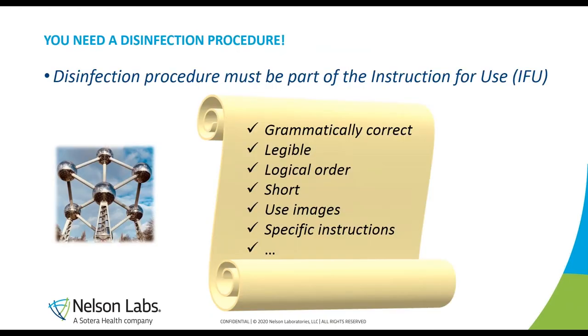Before we start, you need a disinfection procedure. If you don't have any procedure to validate, we cannot start our journey. You must have a procedure, and it must be part of your instructions for use. The information in your instructions for use should be logical, readable, short, and clear for the end user — use images and specific instructions. If you don't have a procedure, you can rely on experts to design one with you. But it is the procedure which you're going to validate.